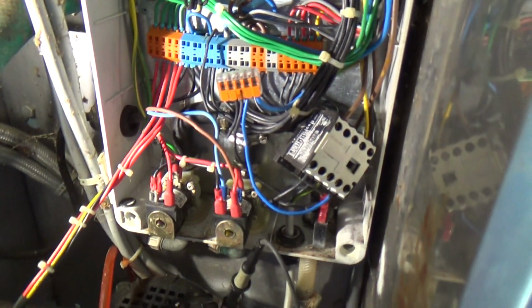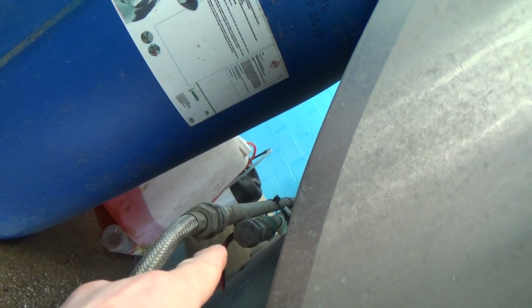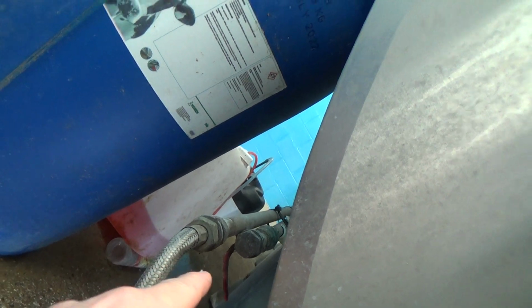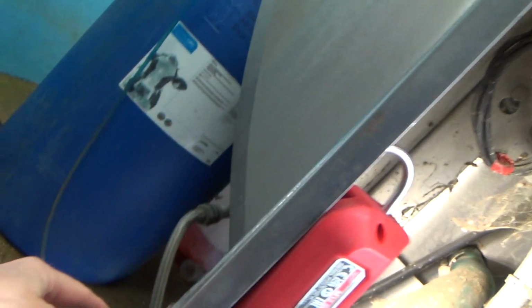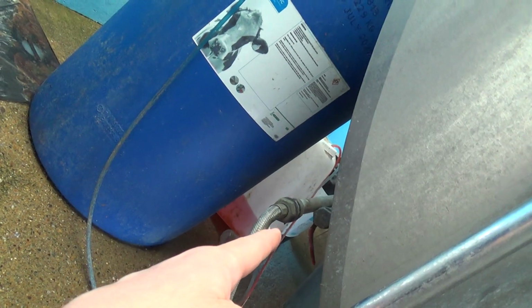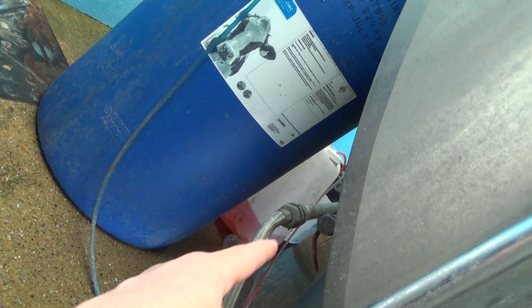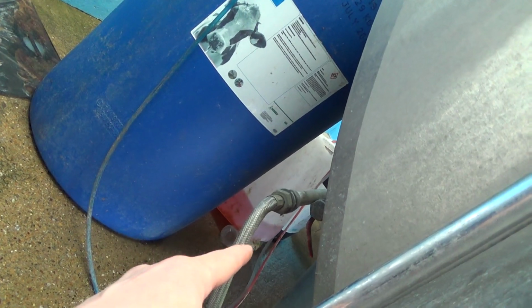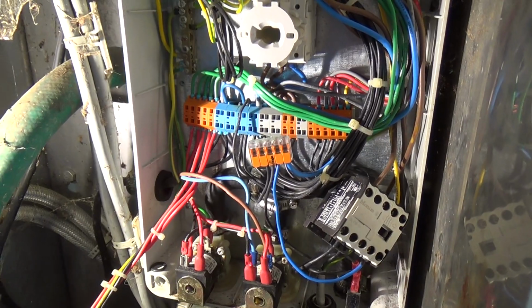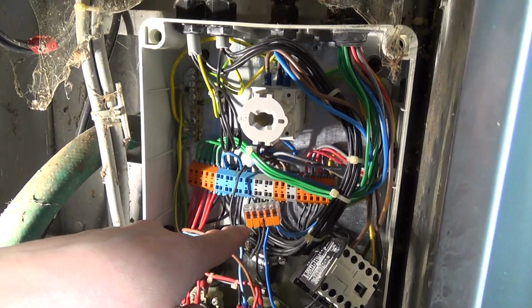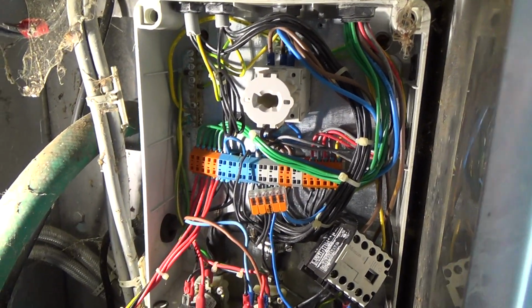There's another pump I can hear whirring away when the cold comes in, because it's been capped off there, so they used to run the hot and cold in along there. They've brought this other hot one in. I think they've got a biomass boiler or something, so that's off of that, and they've just capped off the existing one. Well, that other pump may run kind of dead-headed when it's filling with hot water, and I can hear it whirring away in the background, so we need to work out which one of these wires is doing that and test that as well.